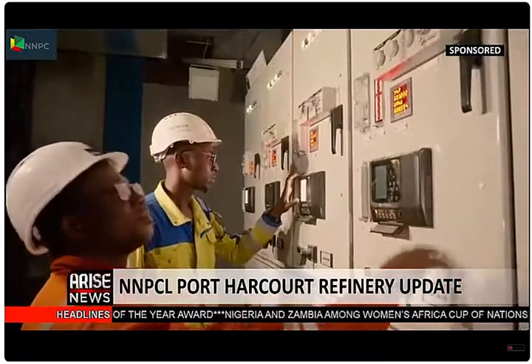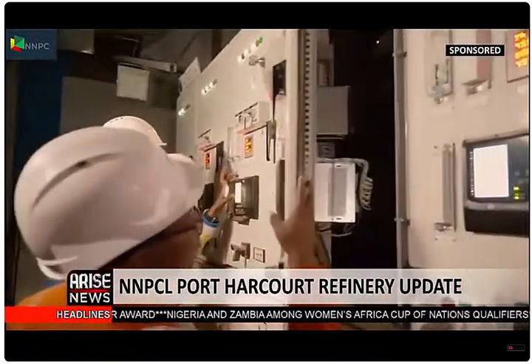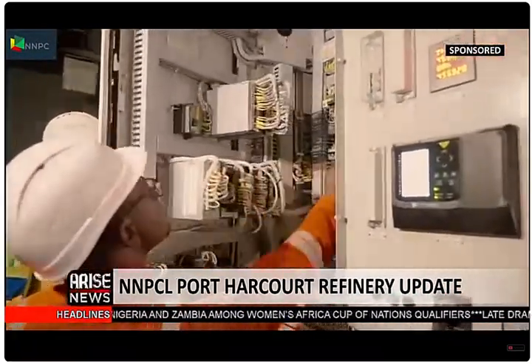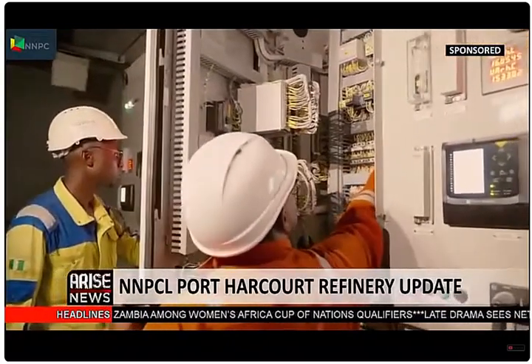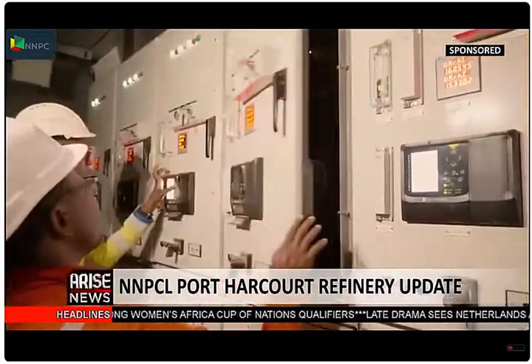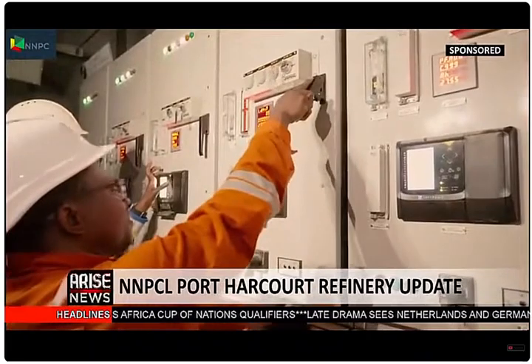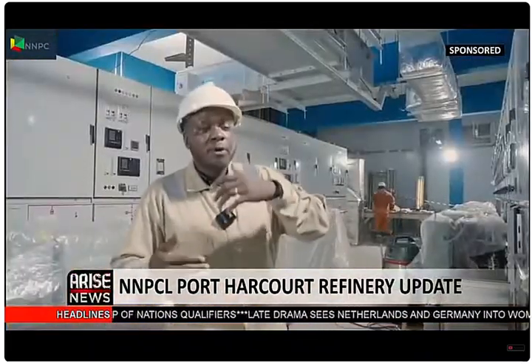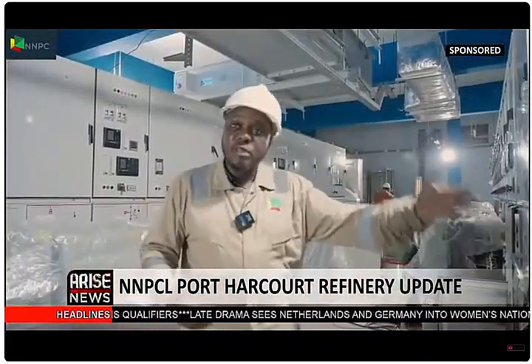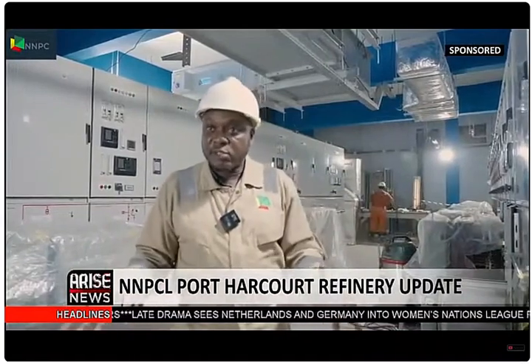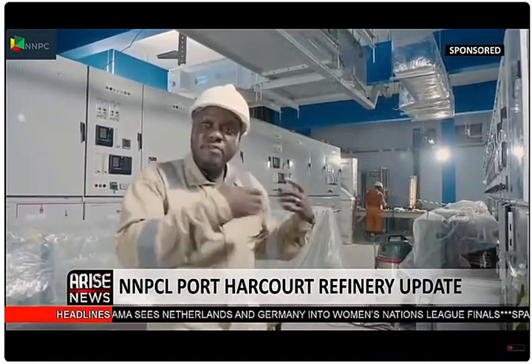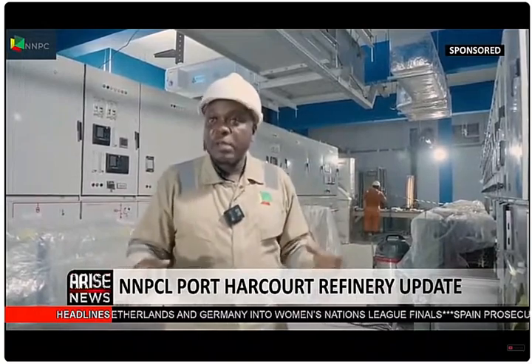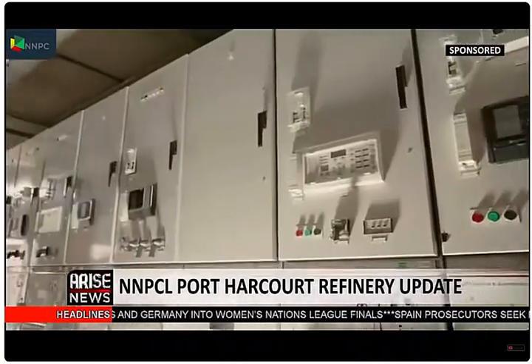It's designed in such a way that the new and the old refinery, we call it old, although everything there has been replaced and it should change the name from old to new now, but it's designed in such a way it supplies Refinery 1 and Refinery 2 power. So from here, you can send power to Refinery 1. Even if there's an issue there, this place stays up. In Refinery 2, even if there's an issue there, this place stays up. So here, no matter what, has to be up.